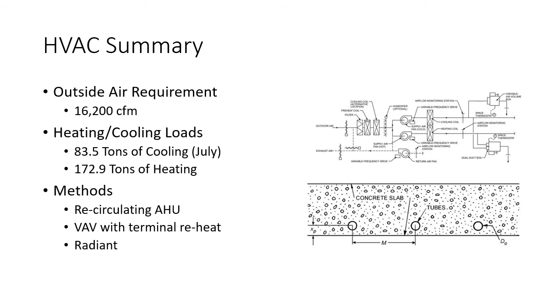So we're doing this through using a recirculating air handling unit, VAV boxes with terminal reheat for each of the zones in the building, and radiant heat for the zones which tend to be a little cooler, such as the ones that are on the outside of the building, just to supplement how much heat we're going to have to push through our air handling unit.